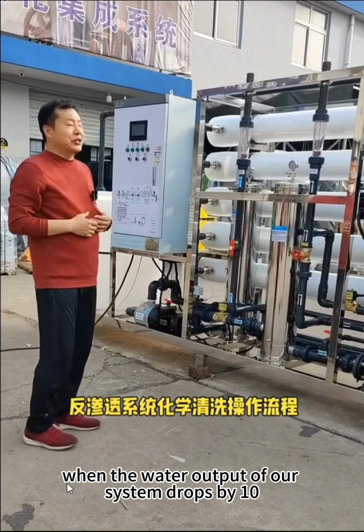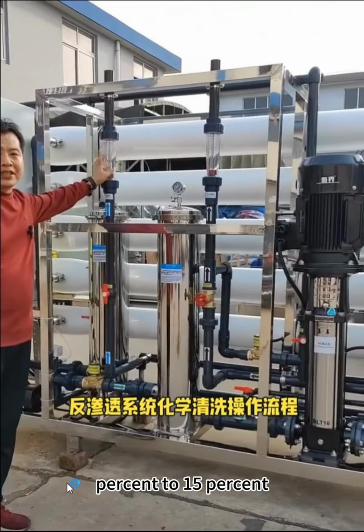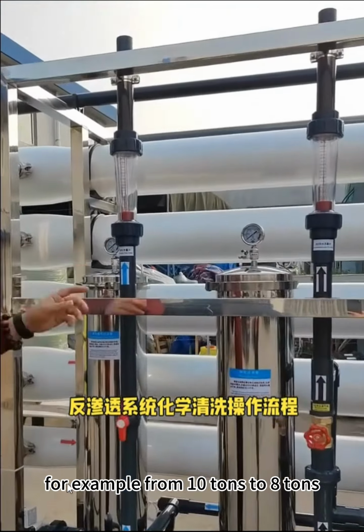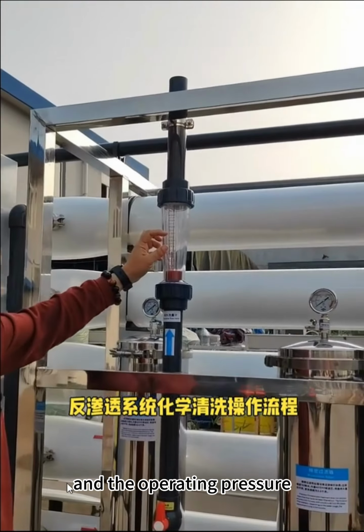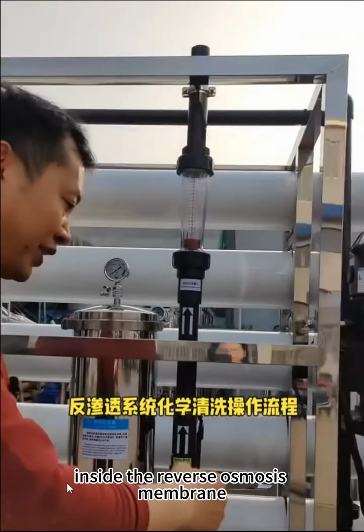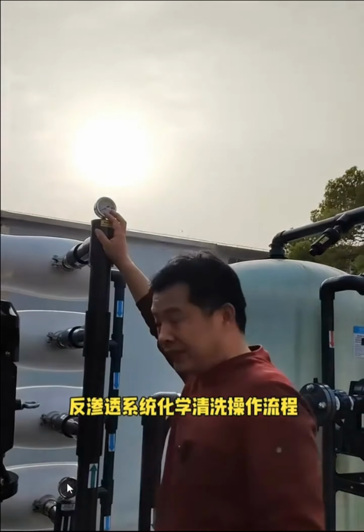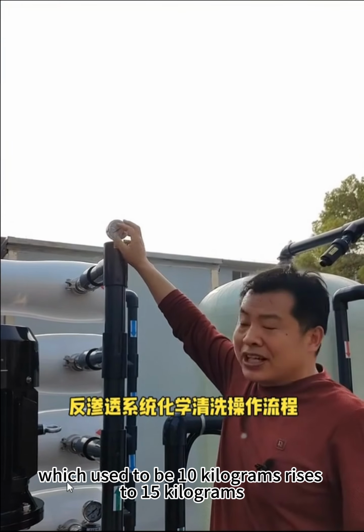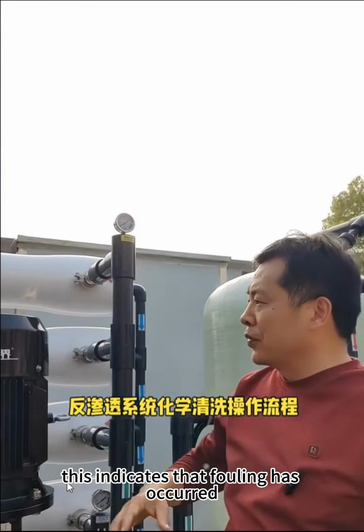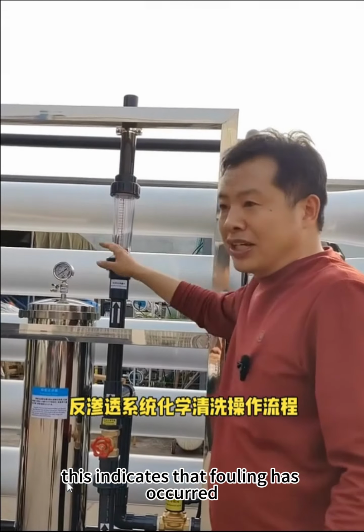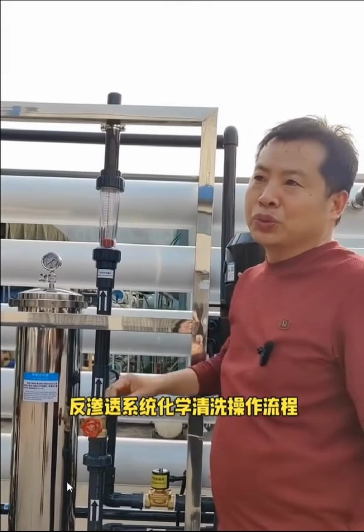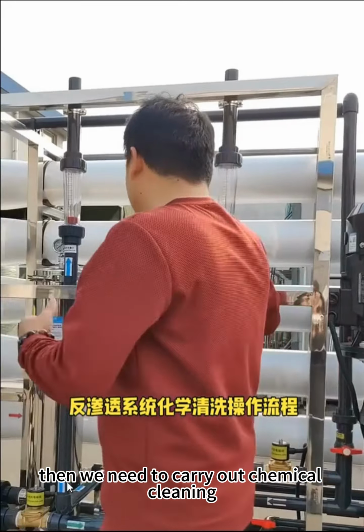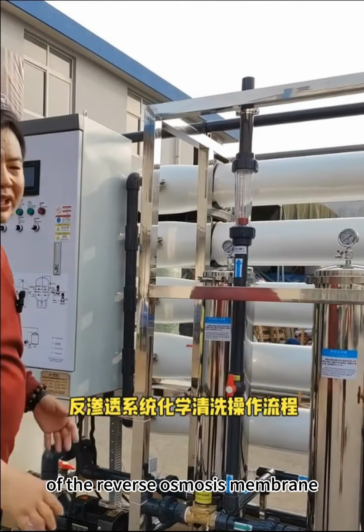When the water output of our system drops by 10% to 15%, for example, from 10 tons to 8 tons, and the operating pressure inside the reverse osmosis membrane, which used to be 10 kilograms, rises to 15 kilograms, this indicates that fouling has occurred in our reverse osmosis membrane. Then we need to carry out chemical cleaning of the reverse osmosis membrane.